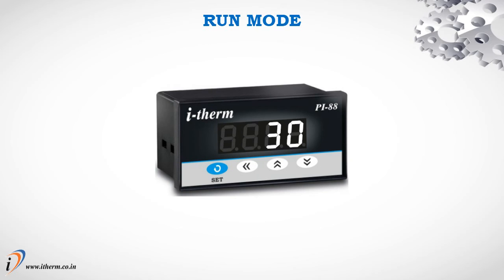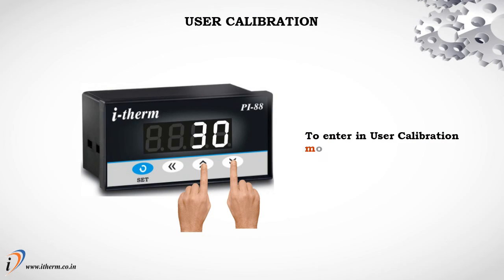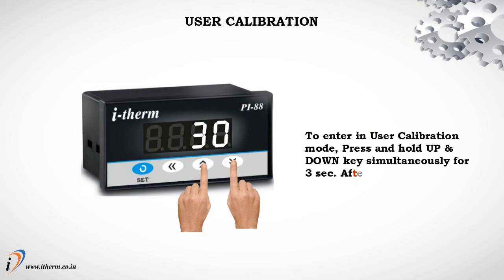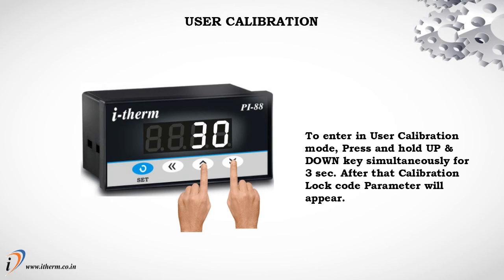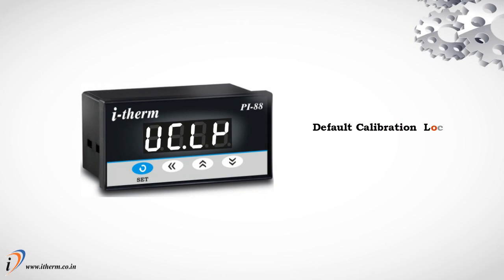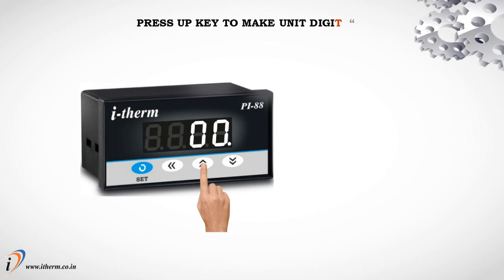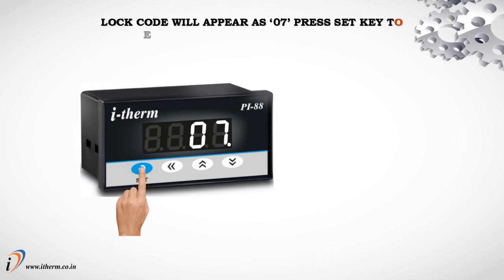Run Mode. To enter user calibration mode, press and hold the Up and Down keys simultaneously for 3 seconds. After that, the calibration lock code parameter will appear. The default calibration lock code is 7. Press the Up key to make the unit digit 7. The lock code will appear as 07. Press the Set key to enter the calibration parameters.